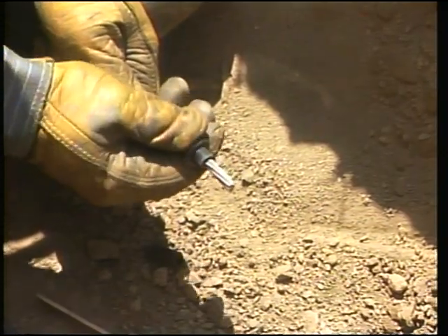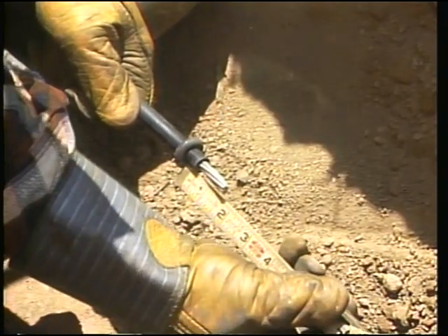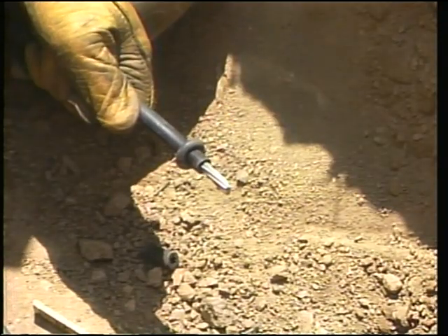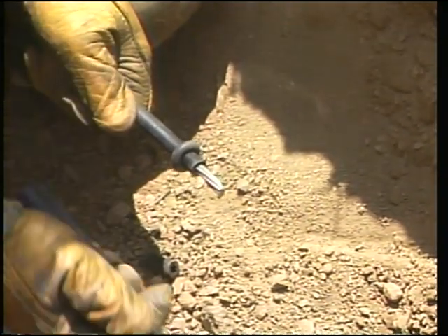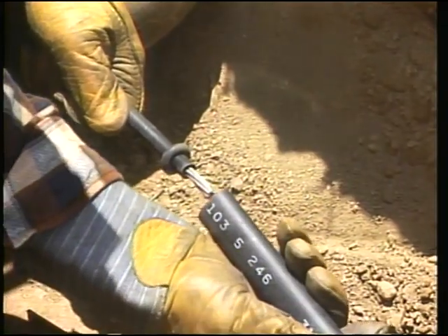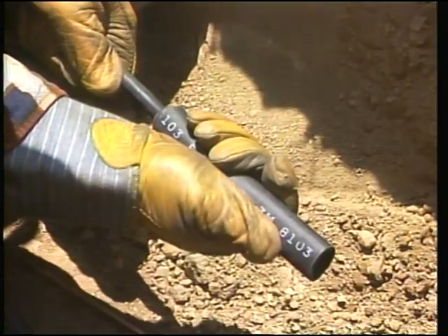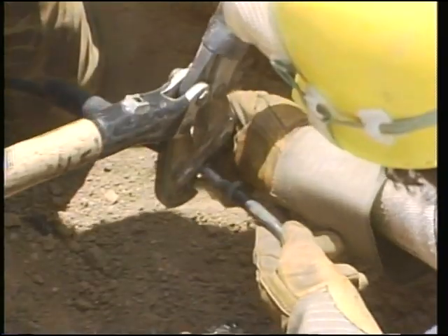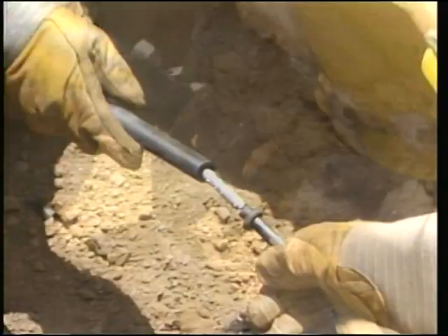To install the splice tube, an O-ring is first placed on each cable at the recommended distance. And as with the other splices, the rolling ring tube will be installed over a compression connection. The insulating tube is then slipped onto one cable over the O-ring and rolled down the cable to make room for the conductor splice. Then the compression splice connector is installed as before, according to the splicing instructions.